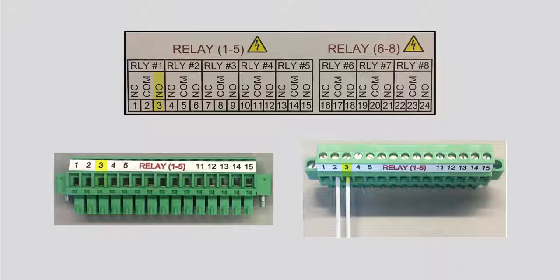In cases where the interfaced circuit demands relay contacts with a higher power rating, an interposing relay is required. Power source voltage should be wired to either the normally open or normally closed contact.